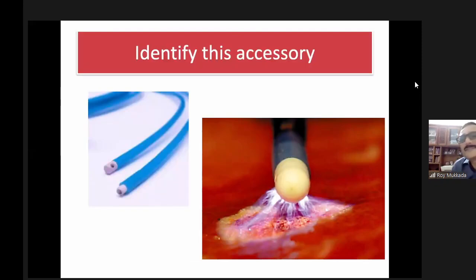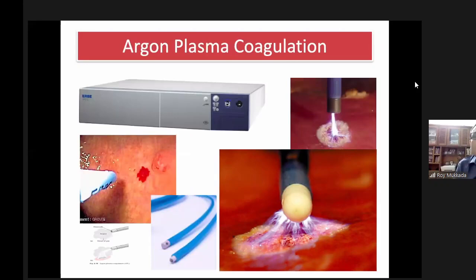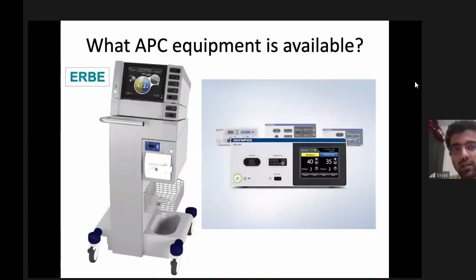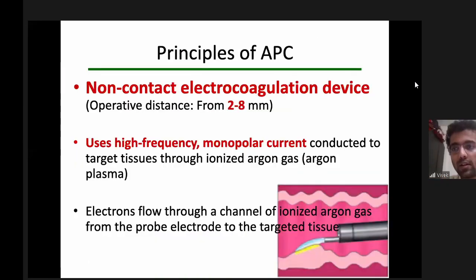What is this? This is an APC catheter, argon plasma coagulation. Exactly. So here you can see that it's a non-contact method. What other differences are there between this and the heater probe? In APC, there are three kinds of devices: one can be radial, one can be side, and the third is on the end. It is basically argon-based electrocoagulation, while the heater probe is contact-based coagulation. Here it is non-contact, and the electrons flow through the channels, ionized argon. That's the basic difference.